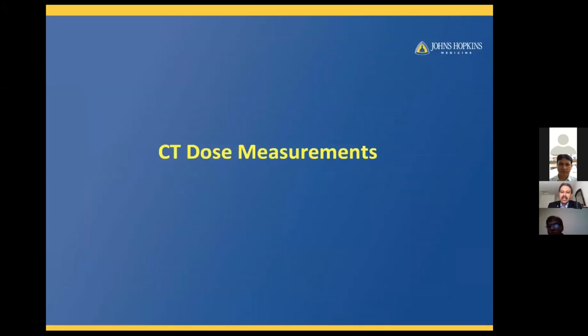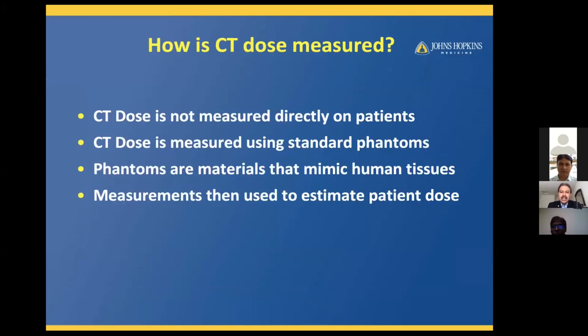Now, let me talk about the actual CT dosimetry. I'm going to talk about the fundamental physics behind it. Just as a disclaimer, when we say CT dose is measured, we do not actually measure anything with the patient. It is indirectly measured using standard phantoms, which are materials that mimic human tissues. I know many of you are practicing diagnostic physicists involved in dosimetry, so you are familiar with these phantoms. These phantoms are used for measuring CT dose, and from these measurements, you can estimate a patient dose.